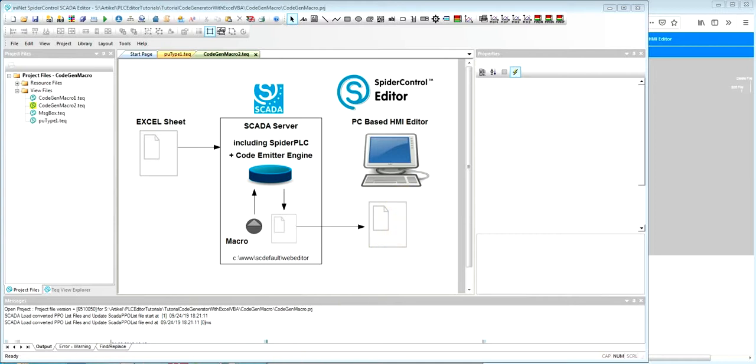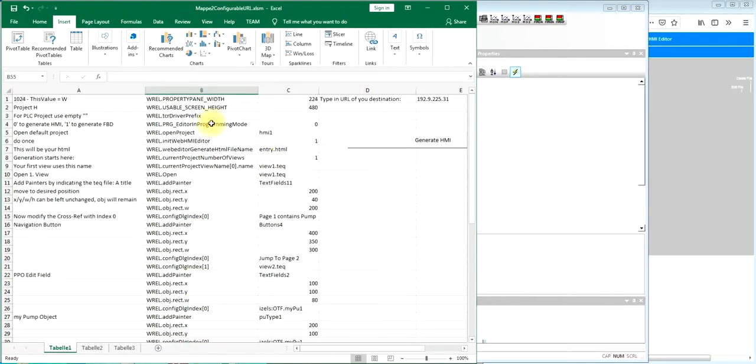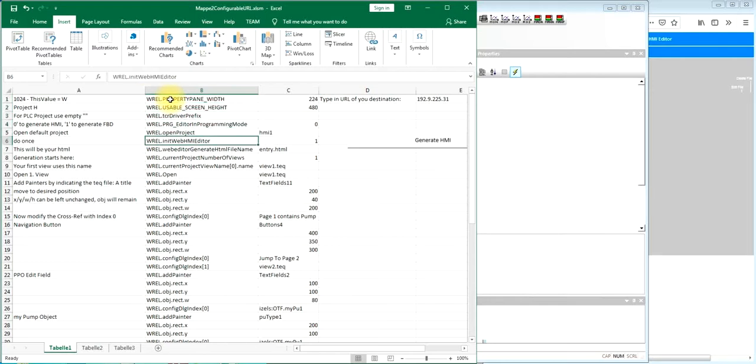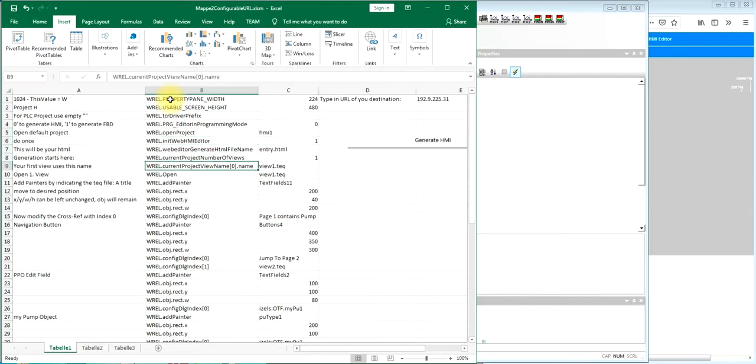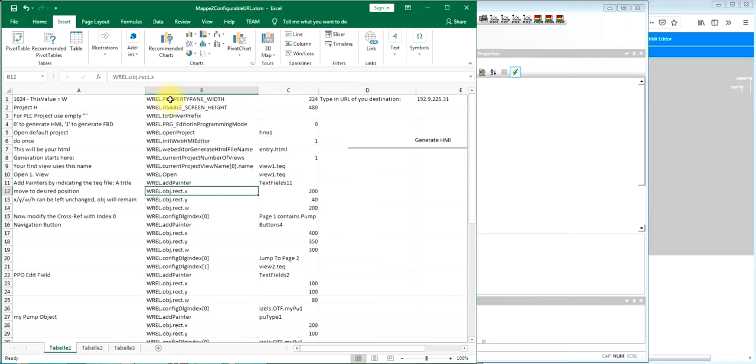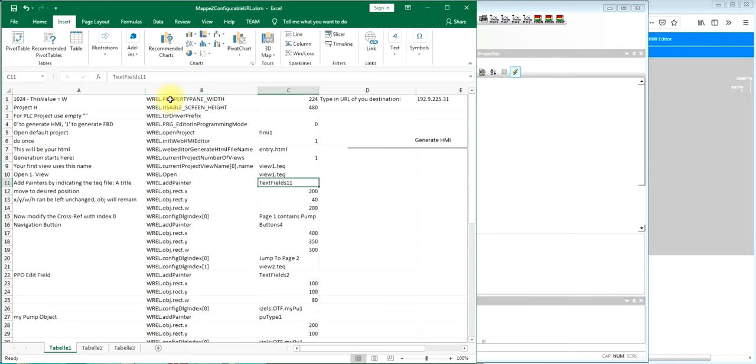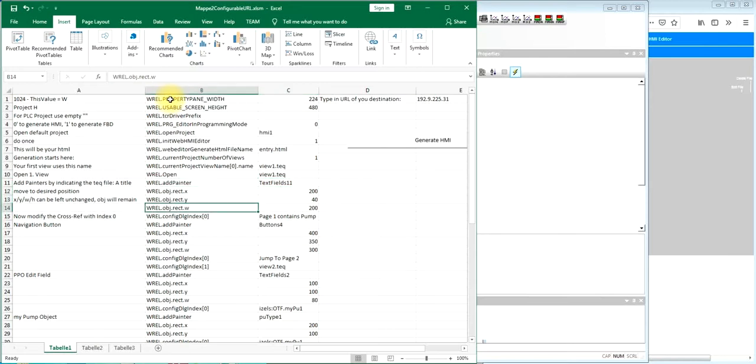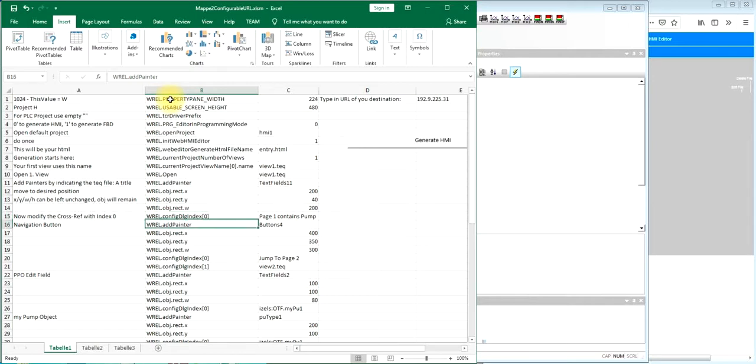We will start with the Excel sheet. The Excel sheet contains this row of commands which are sent to the SCADA server. It will open the project, open the tech file and start adding objects. It will add the objects just by calling the name of the respective text field. We will then modify position x y w and we modify internal references to texts to other variables.